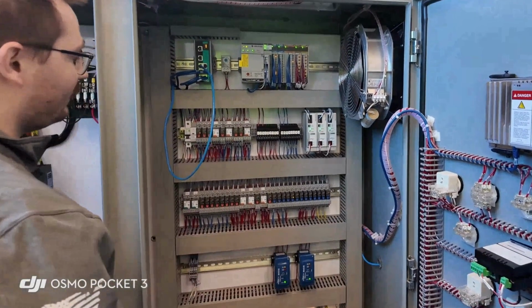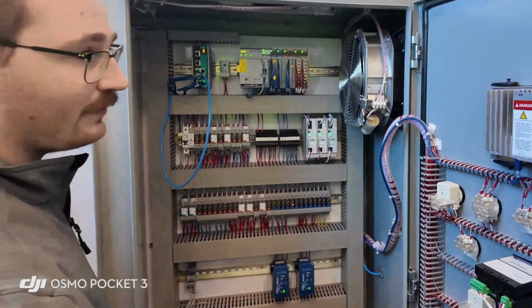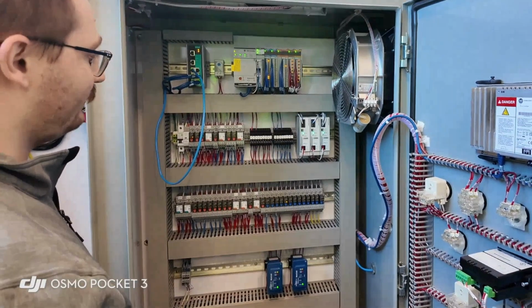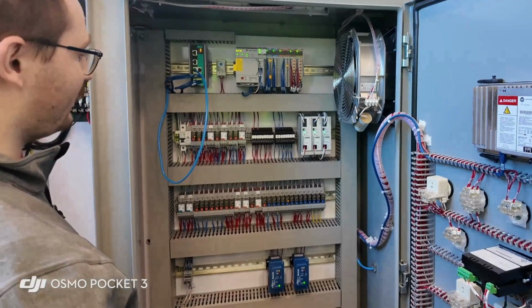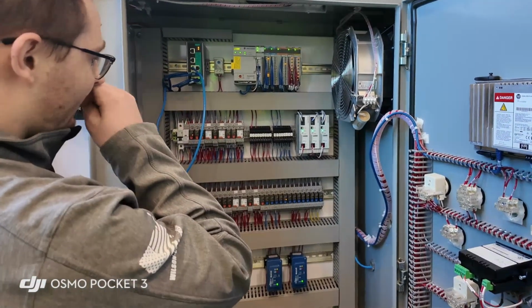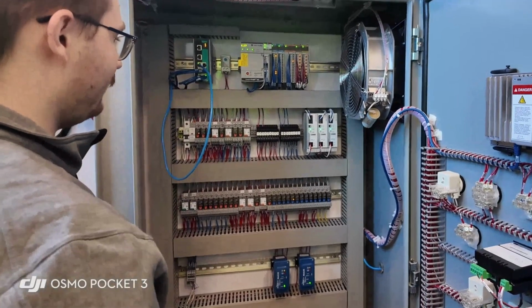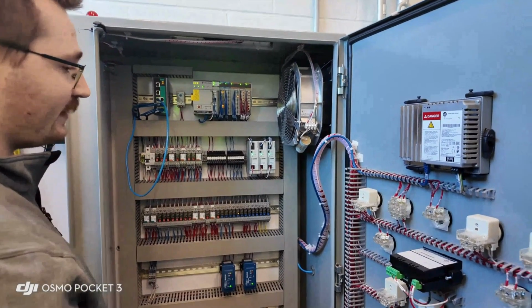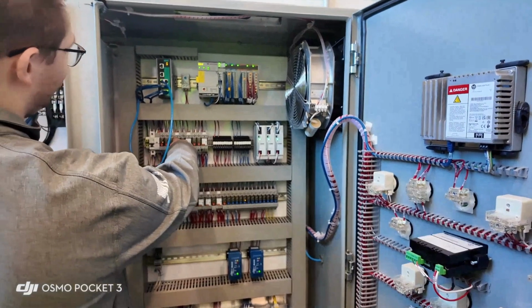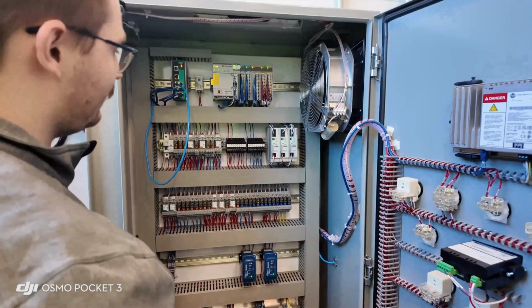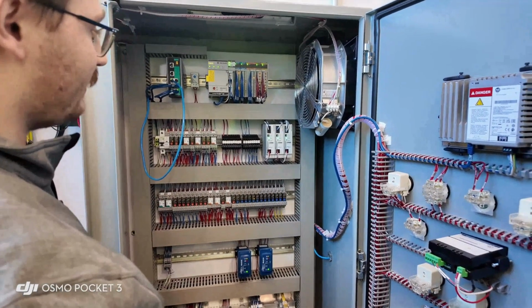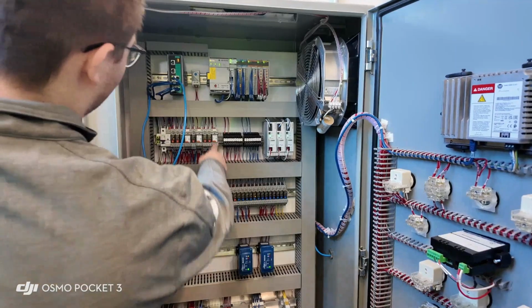There's the LSLL, which is the very low level. That just sends you an alarm saying it's at a very low level, and when it comes off, it locks it out. Next to that is our CRH, the control relay high, so that's what energizes the backup. LSHH will actually activate CRH, and CRH is what gets latched in. This is what gets reset, backup control.